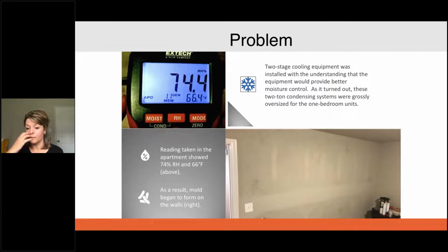This is one of the interior walls when we went into this apartment, and it happened within a week. They actually had 5 units that looked like this, and 2-stage systems - 2 tons on about 700-800 square feet - because they were trying to run the 2nd stage to get dehumidification, which is what they were kind of sold for that system. But as a result, the residents were uncomfortable and they just kept lowering the thermostat. When we went in, we were at almost 75% RH and 66 degrees in this apartment.